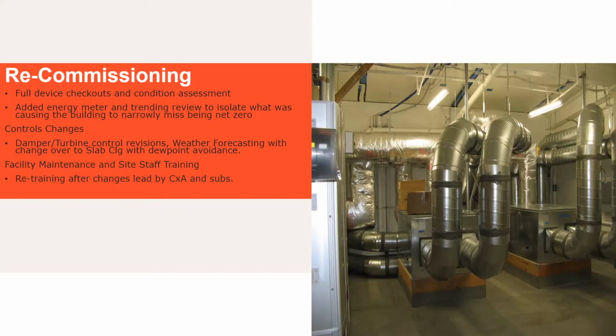Knowing that, then we took a look at adding weather forecasting. We were lucky enough that web-based data was available that could get inputted into the system, so they could start grabbing it. I think this was 2015, 15 is when I was there. And you could start pulling the next 5-day, 7-day forecast. And we put in programming that if we saw 85-degree, I think we landed on 2 85-degree days in a row, both adjustable, how many days in a row and what temperature, that it would automatically do slab cooling, and it would start doing flush, pre-cooling of the whole building.